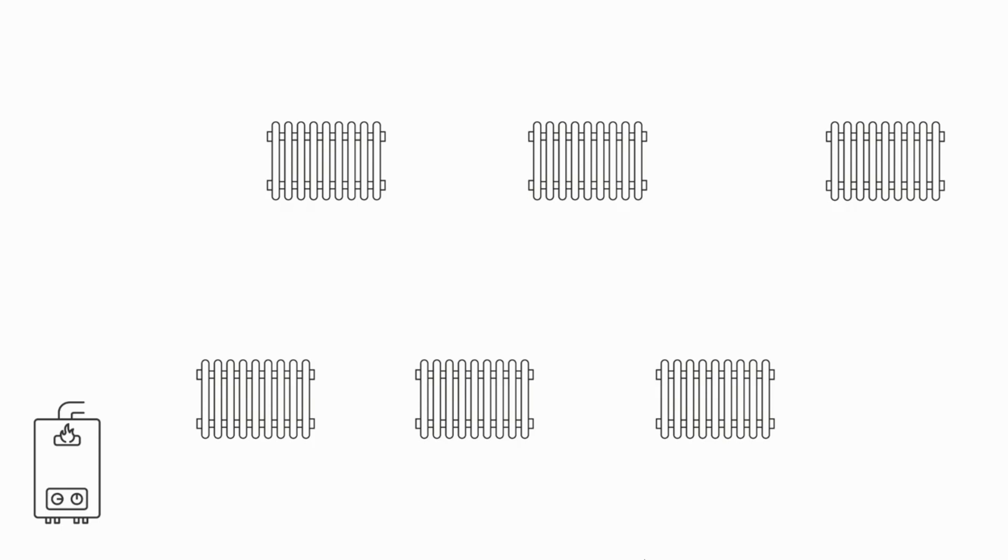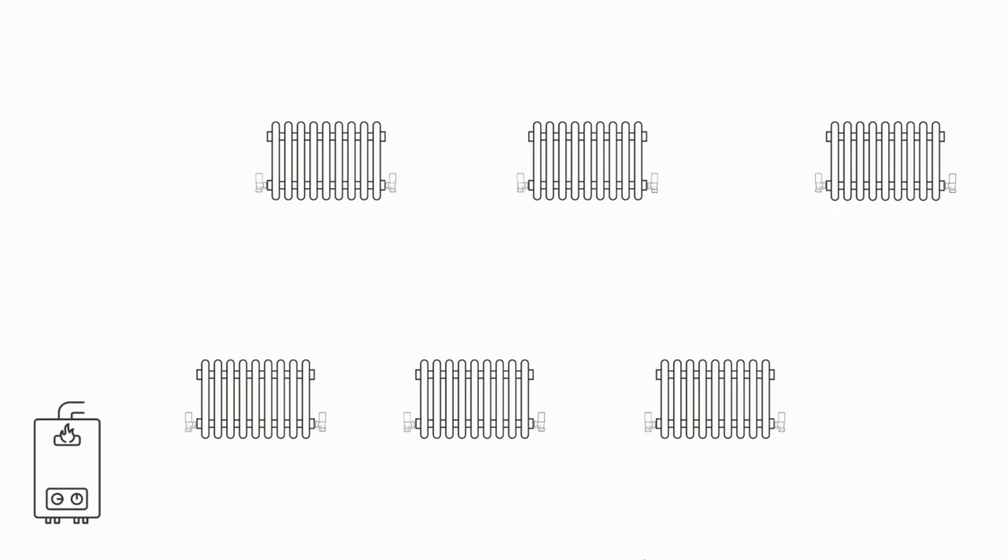What you tend to find is that the radiators that are closest to the boiler tend to have less resistance to flow than ones further away, and balancing looks to even this out across the whole of the system. To do this we need some way of restricting the flow into the radiators so we fit some valves. It doesn't matter whether the radiators are being controlled by manual valves, whether there's a lock shield at either end, or whether at one of the ends there is a thermostatic radiator valve. Ultimately a radiator system needs to be balanced regardless of the method of control for the actual radiator itself.